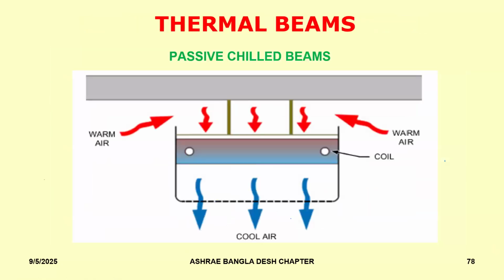Another thing that I want to leave you with is the use of chilled beams. There is something called a passive chilled beam where we don't have any fans or anything. All we have is a cooling coil which has got chilled water circulating in it. When I use the word chilled water, I want to be a little careful here because the temperature of that coil should be above the dew point of the room. So what happens really is a convective process. The air in contact with the coil will cool down, and because it's cooled down, it will drop into the space, and then as it picks up heat from the people and the processes or whatever is happening inside the space, could be a fabric load, etc., it will get warm and rise up and again come and recirculate. So that's called a passive beam because we're not using any fans or anything.